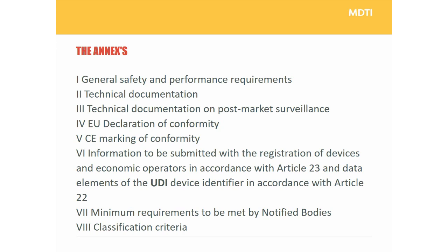Annex 1 talks about general safety and performance requirements and sets down the expectations from a regulatory perspective for the design, development and management of products under the regulation. This is incredibly important and is the basis of your declaration of conformity, so it's important to have a very thorough understanding of this. It requires the application of risk management techniques and human factors usability engineering to the design and development of products through to labeling content requirements. It's an extremely thorough listing of requirements, really a move on from the essential requirements in the previous directive.